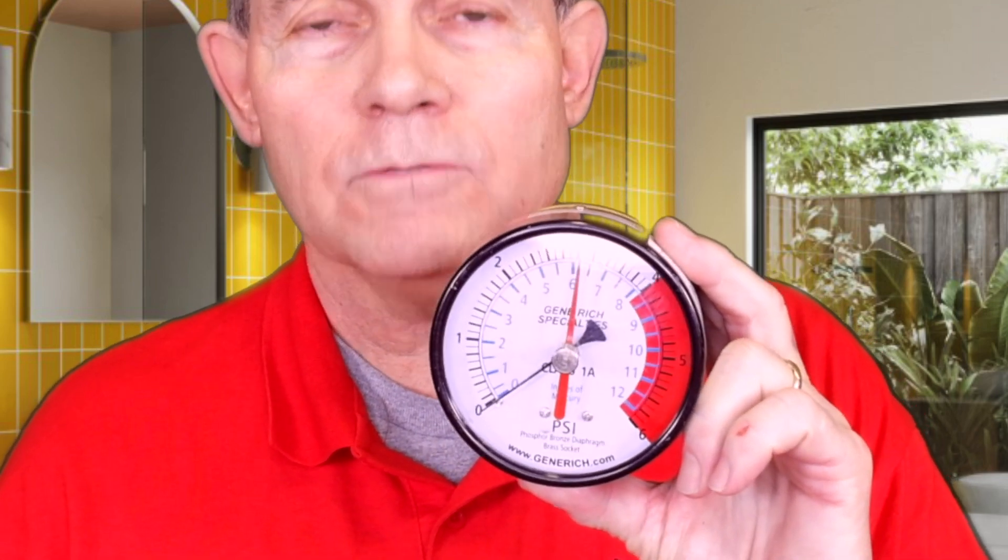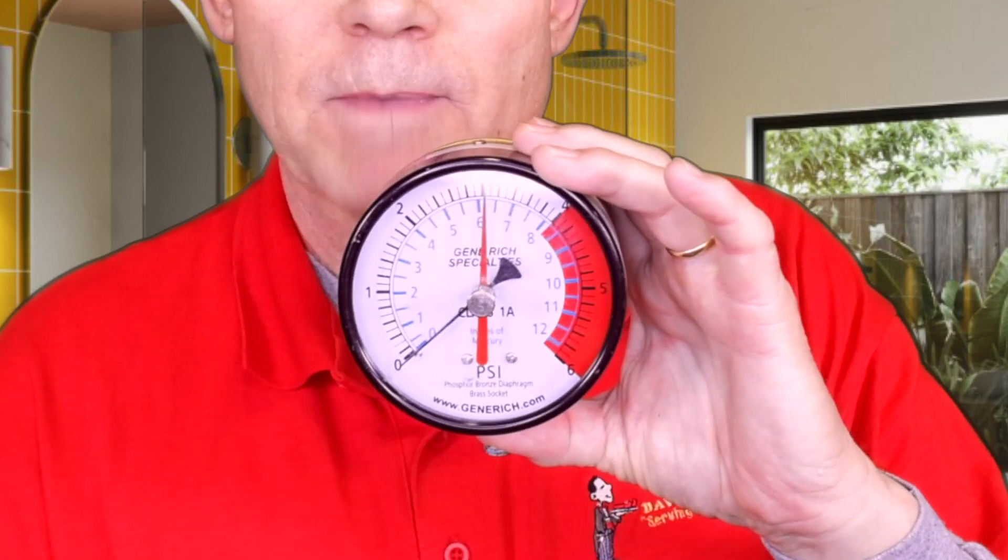How do we know what pressure we're putting on the system? We use gas gauges. These gauges are what we call diaphragm gauges — about $65 to $70 apiece. They're very delicate but also very accurate. They have a needle pointer and a red pointer we set to our target. This particular gauge is a six-pound gauge. Most are either five or six. This gauge is what we'd use to test low pressure gas systems — that means less than one pound, which is the normal working pressure on most homes. We test these systems at three pounds on a five or six pound gauge.